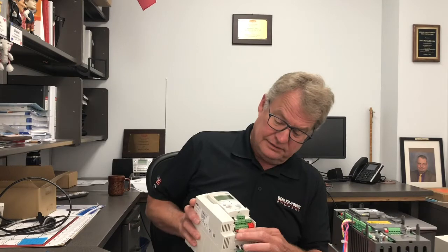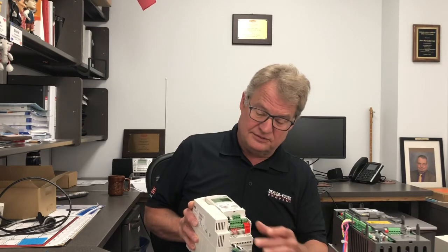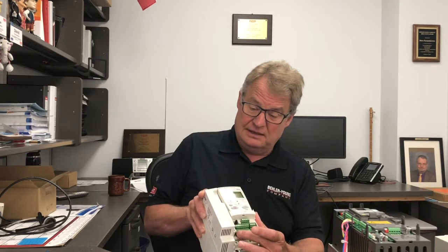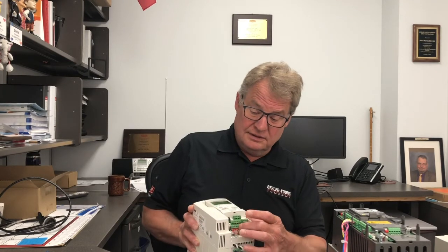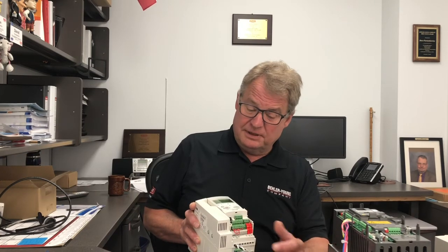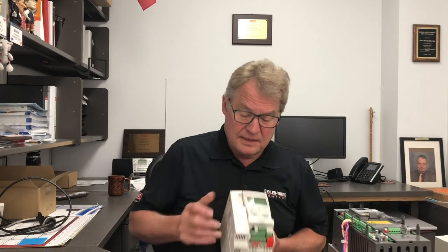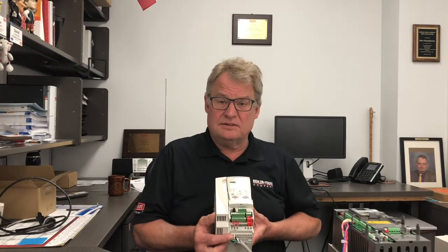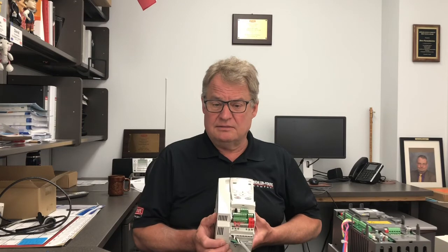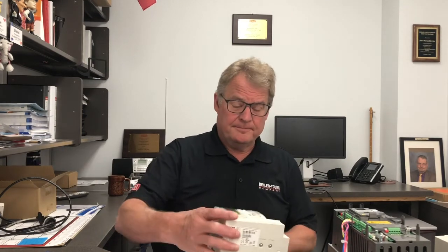On the ACS 320, it's very similar, and there are my terminals here. I have little jumper wires on here just for testing, but it's the same thing. Pink is 24 volts, yellow is low speed, and white is high speed, so I can check right here if I have that call. And here's my incoming power down here: my line voltage coming in and my line voltage going out. So I can check if I have power coming in, and if I have voltage going to the motor.